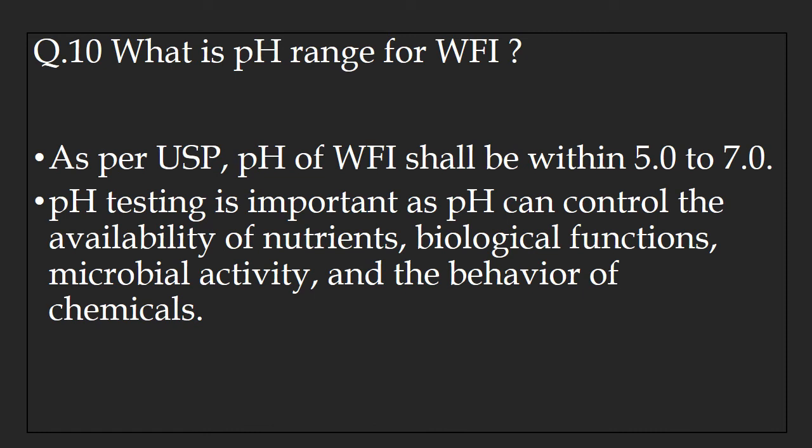Question number 10: What is the pH range of WFI? As per USP, the pH of WFI shall be within 5 to 7. pH testing is important as pH can control the availability of nutrients, biological functions, microbial activity, and the behavior of chemicals inside the water.